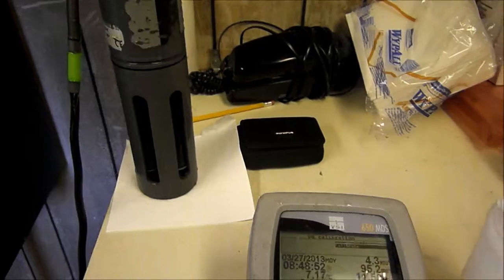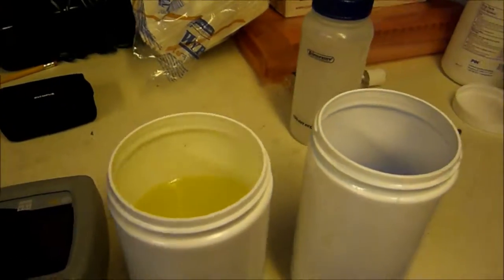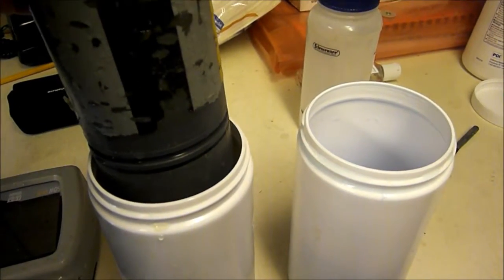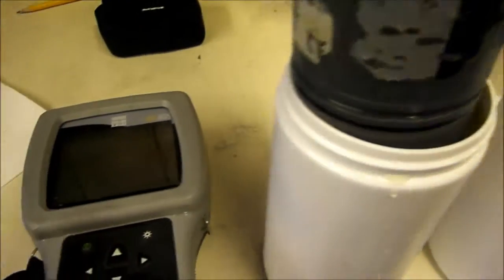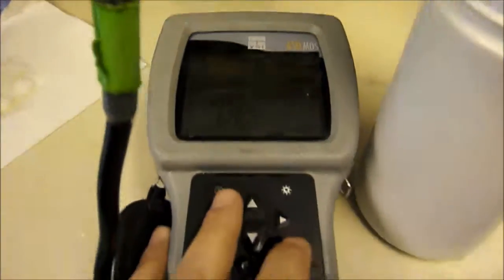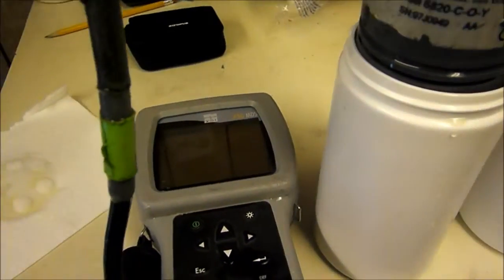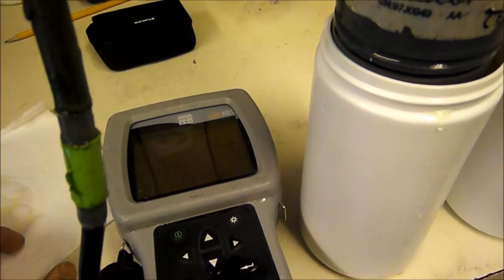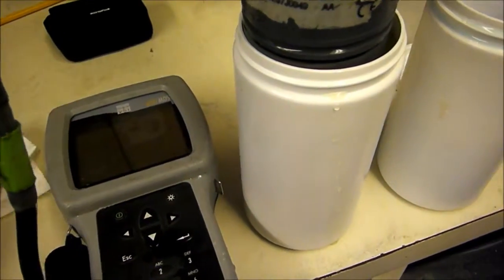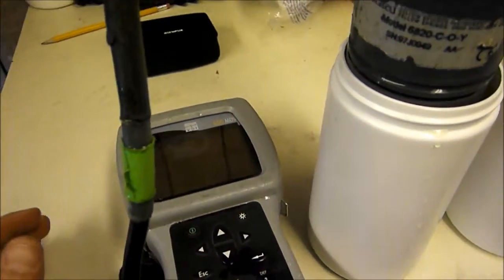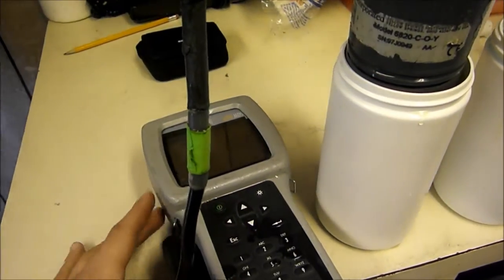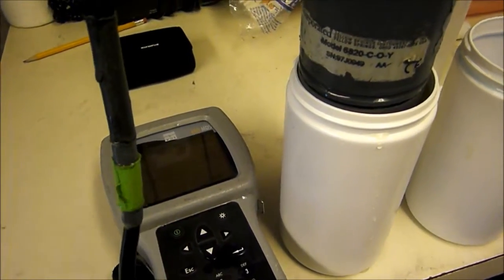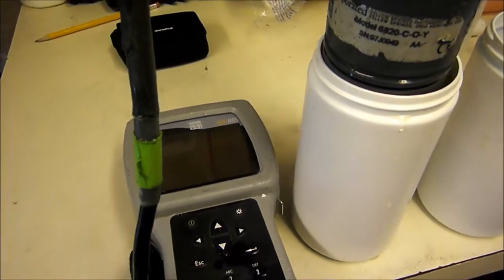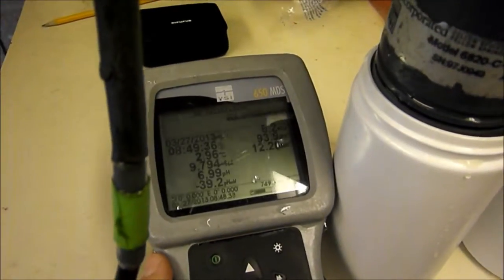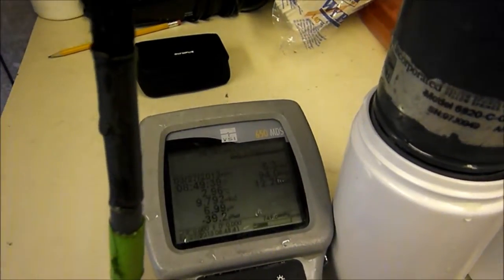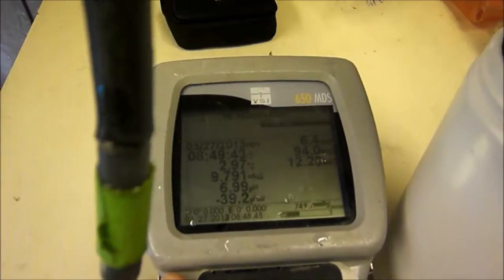Alright, so the sonde is not in the solution yet. Alright, so we're going to let it equilibrate. A couple of maintenance notes. You'll want to keep the glass bulb on the pH probe clean and free of debris. If it's going really slow or readings are jumping up and down, you might want to recondition it per the instruction manual, which includes cleaning, checking on making sure the port's not contaminated with water, maybe soaking it in a pH 4 solution or a hydrochloric acid solution. Again, take a look at your manual.